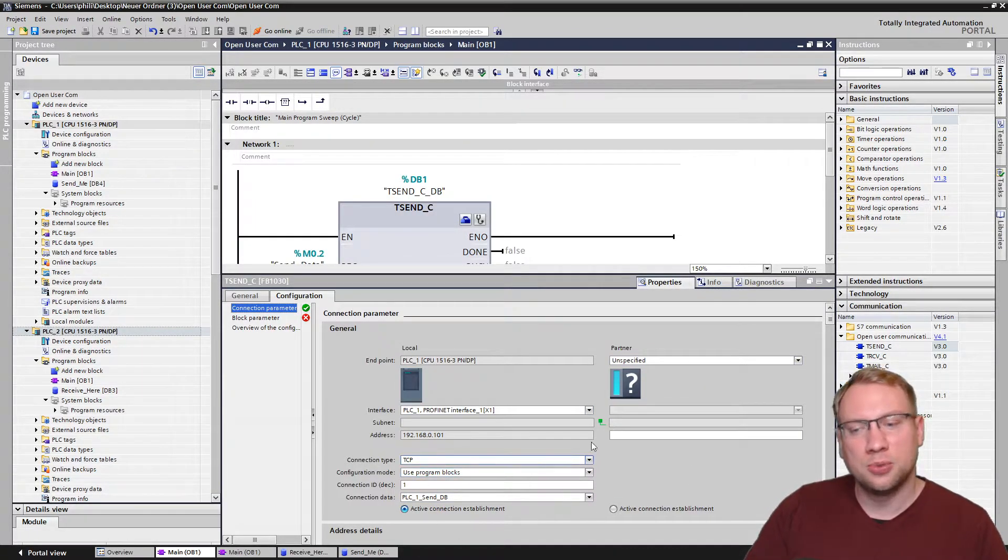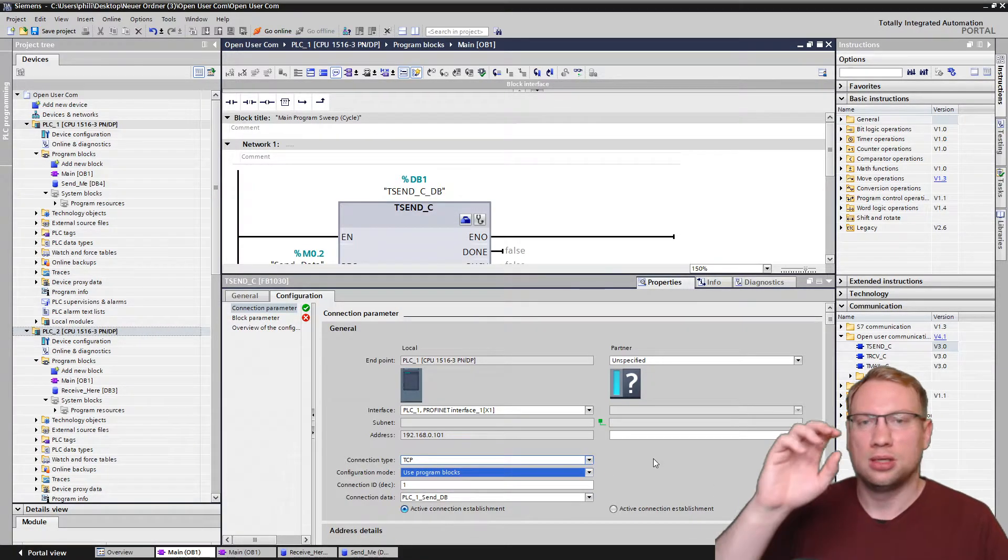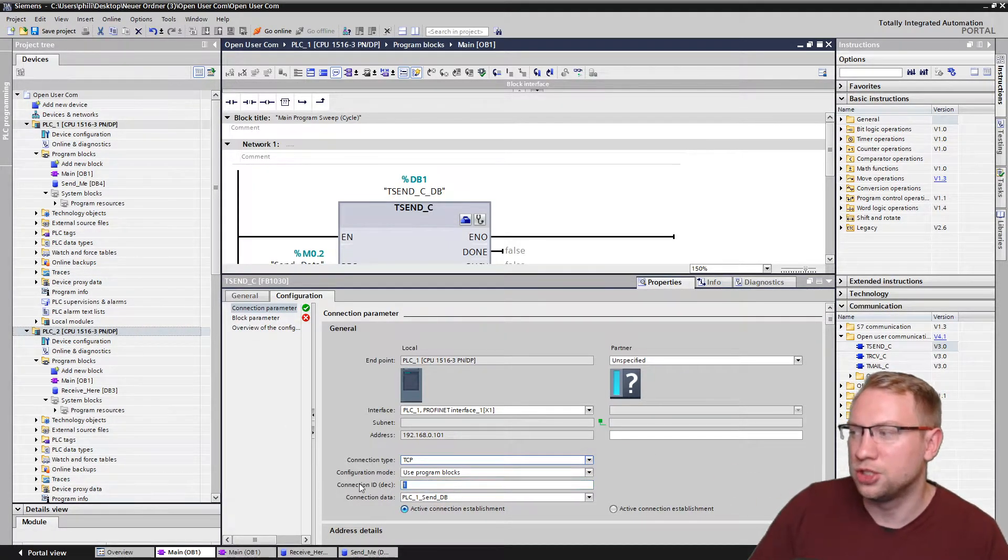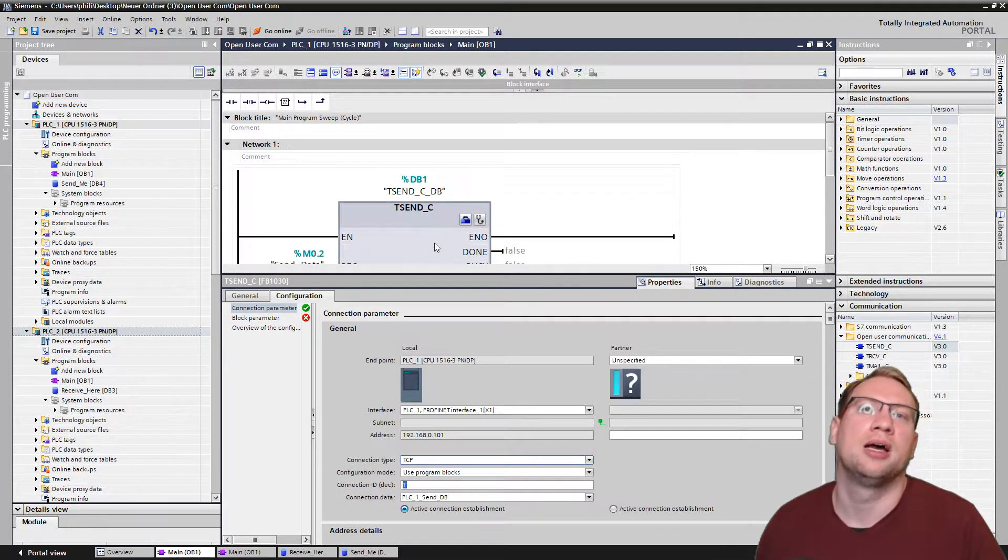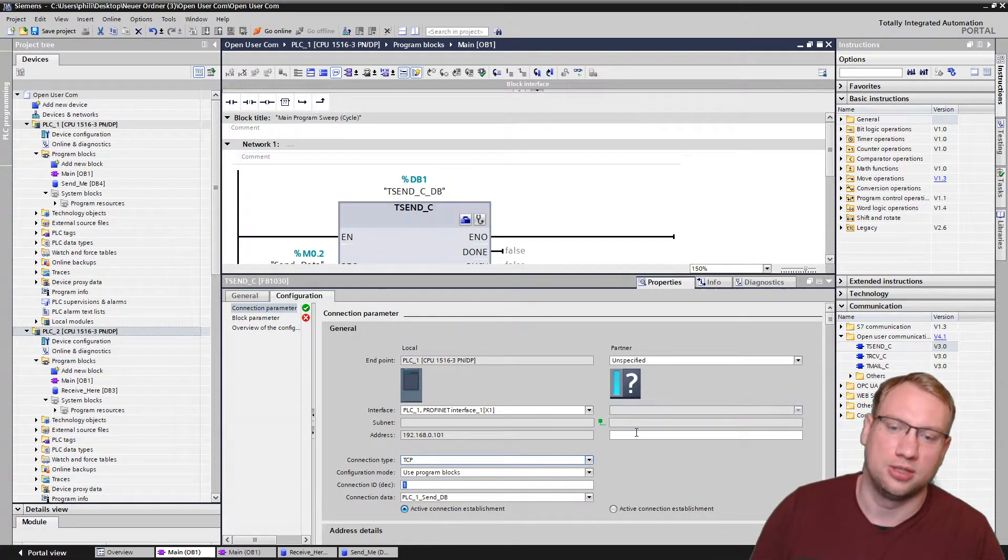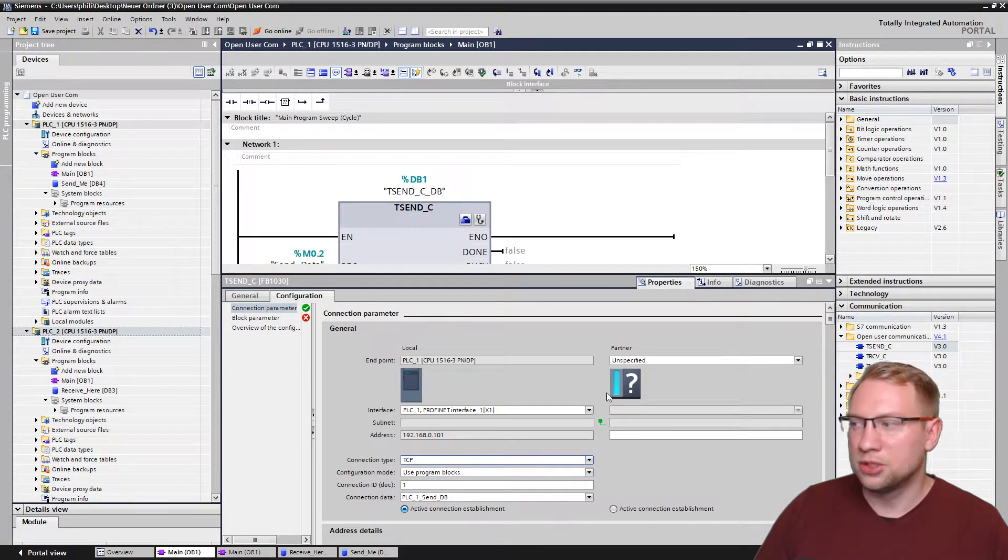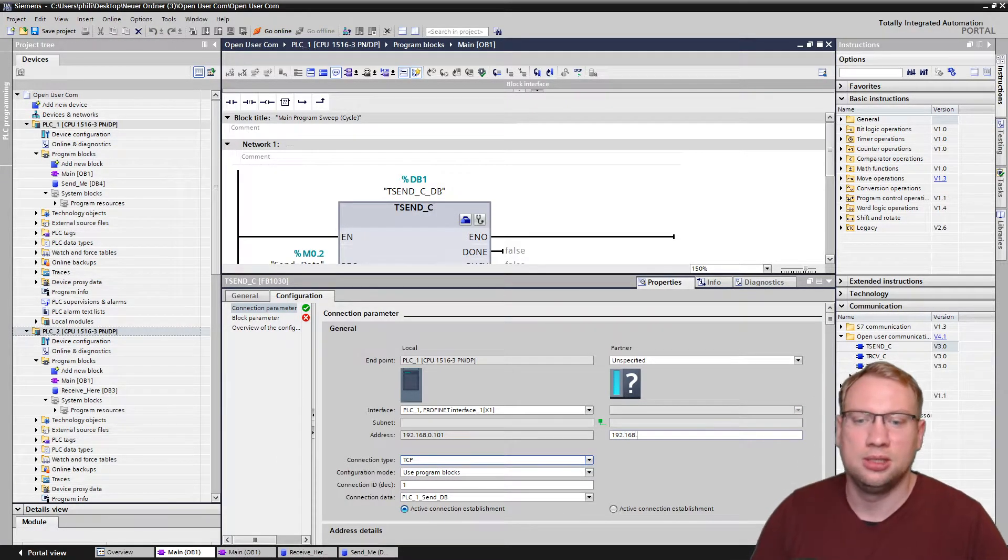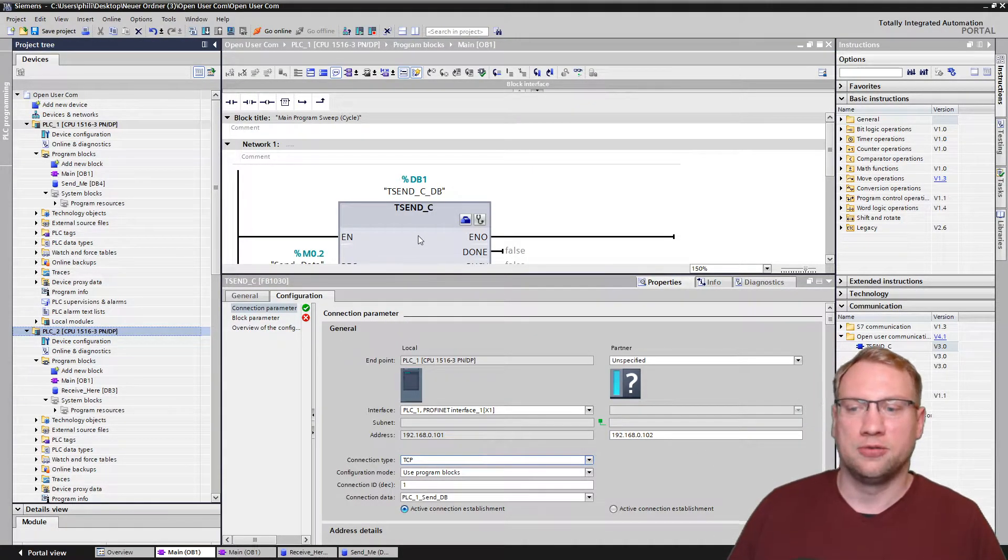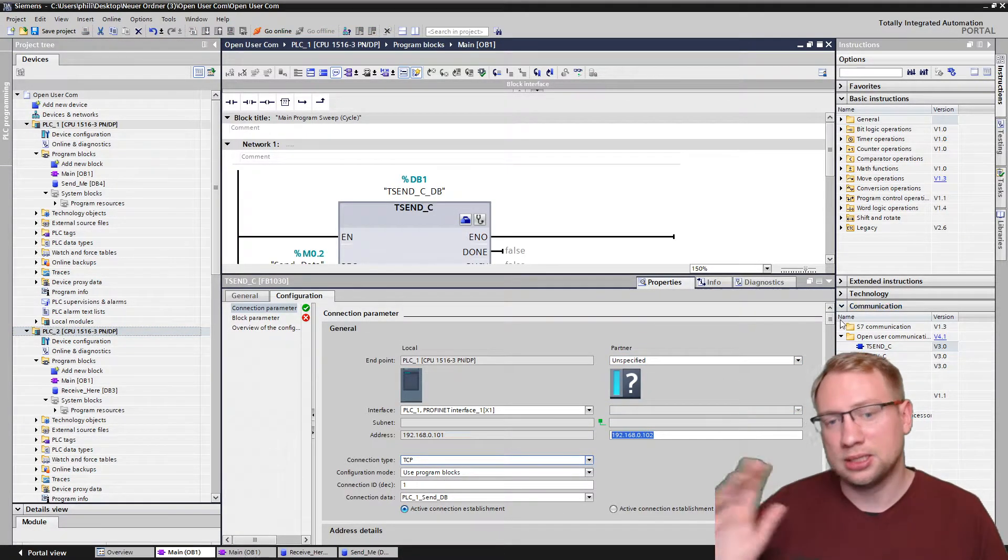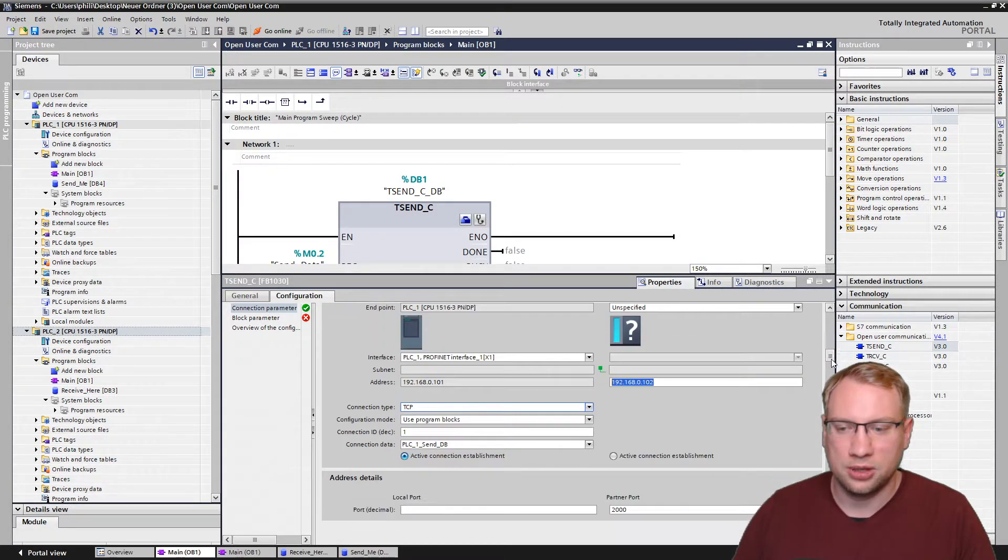What we need to do here is now, we need to create a connection database, where all this data that you see here is stored. New. Then, after we have created one, we could choose now a connection type, a configuration mode. I always leave it as it is. That's the best. The only thing that we need to remember here is the connection ID. If you want to send data to more devices, you will have more of those blocks, and each block should have an individual connection ID. Next thing we need is in the address, we need to put in the partner IP address, and I have given my PLC the 192.168.0.102. This is the second PLC here, so my first PLC with this number sends data to this partner, which could be anything. It does not have to be a PLC.